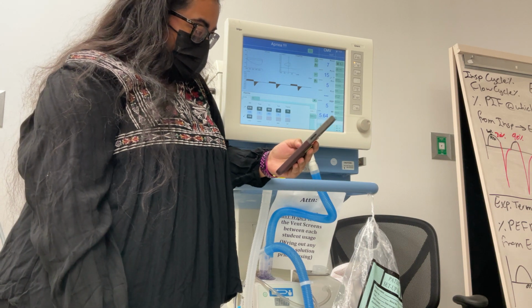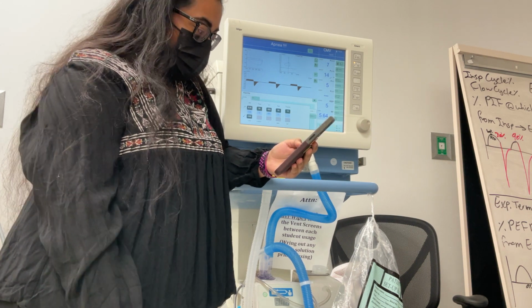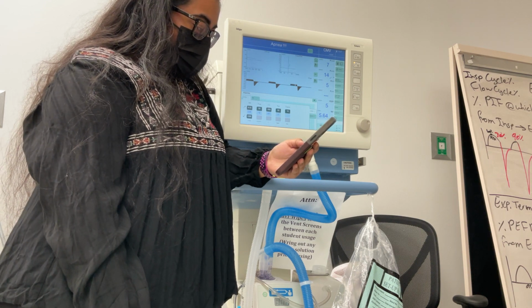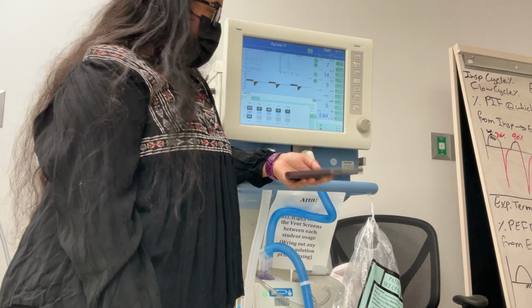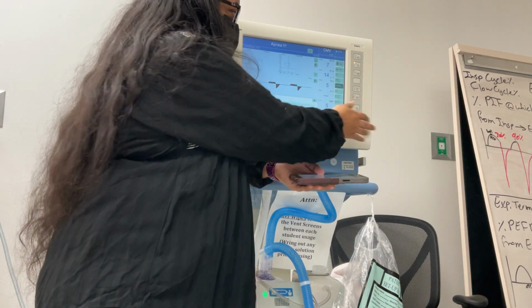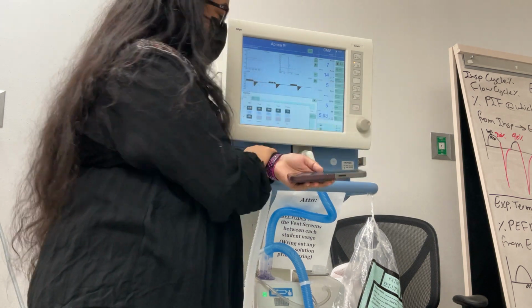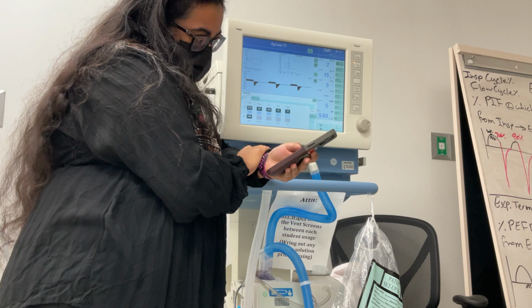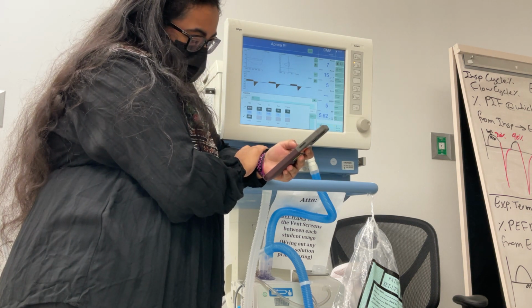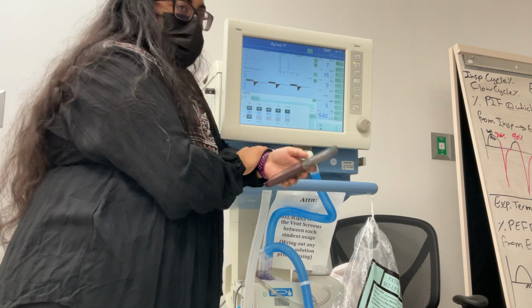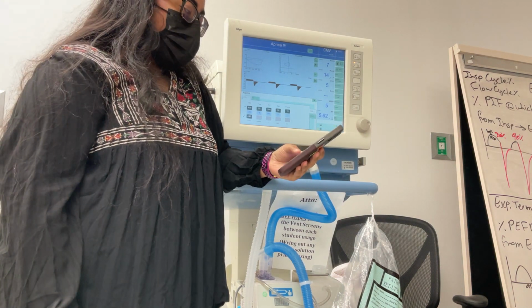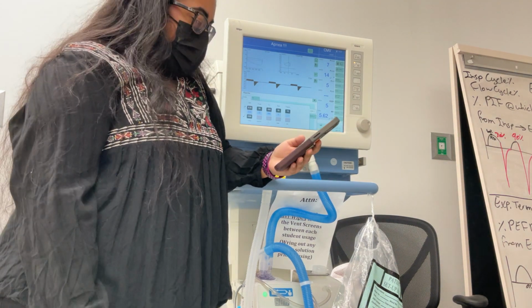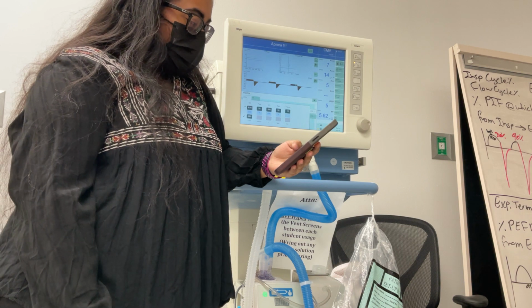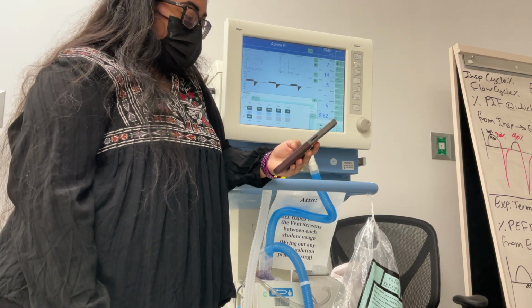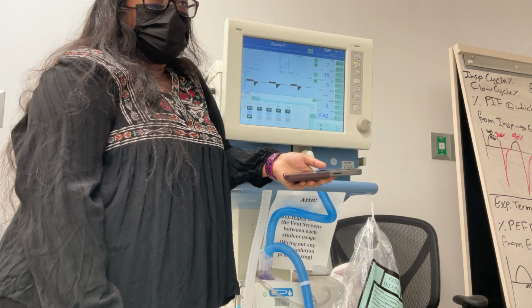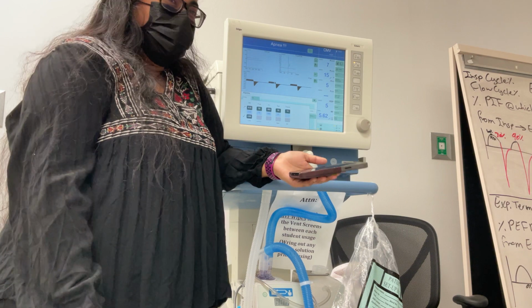What else do we have? Alarms, high pressure alarm, high volume alarm. Everything else you can kind of figure out: suction, O2 suction, hit 100%, cancel. Slope, how fast to PIP, auto triggers, your flow trigger, you'd adjust that. Compliance and raw are always going to be the same. On your checklist, it's going to say auto flow, y'all know that's PRVC. P0.1 we did. And how do you identify a leak and over distension on your loops? Same stuff as before.